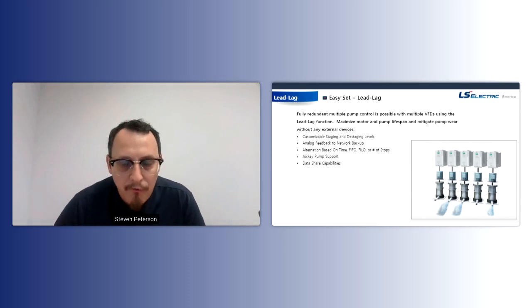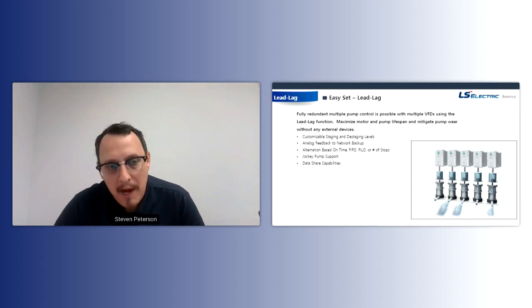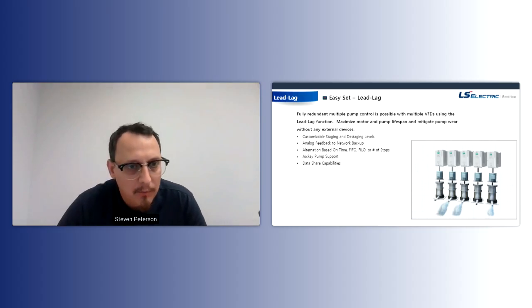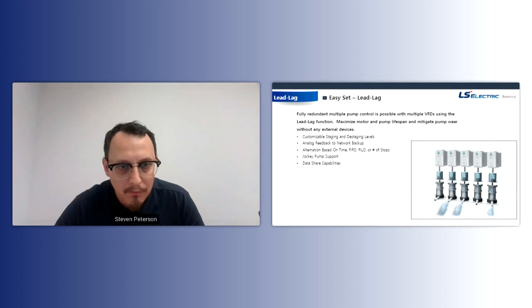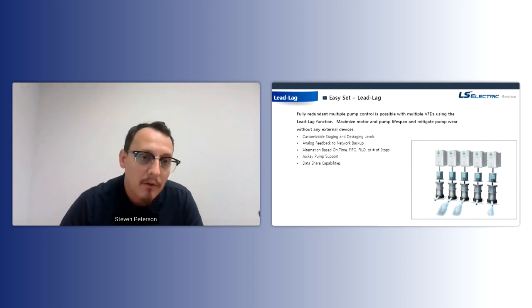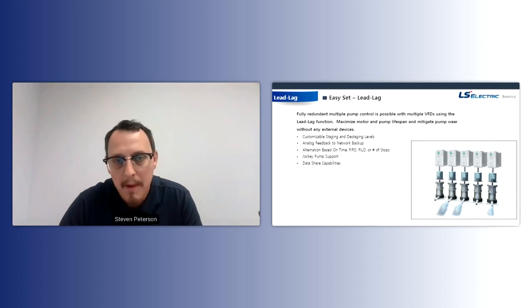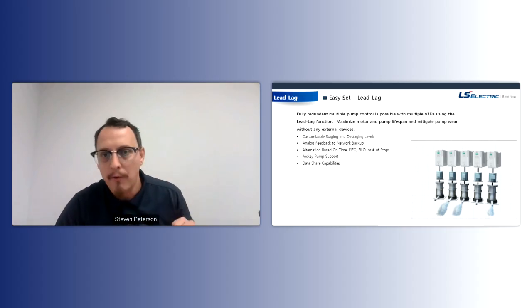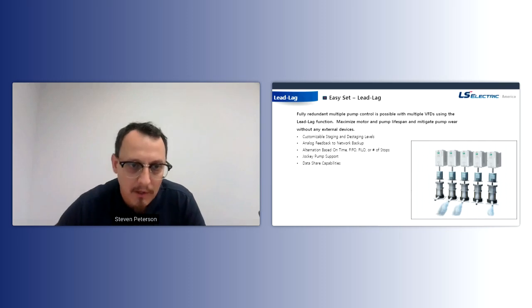Okay. So first, you should note that after you set up the macro, everything is fully customizable. So your staging and destaging levels, your on levels, your off levels, when you need more pumps, when you want to drop out pumps, is all fully customizable. Additionally, you could run analog feedback, or you could have network feedback, and we are adding functionality where you could automatically switch from analog feedback to a backup network feedback. So if feedback is lost, you could look at the backup feedback. So it's fully redundant in that regard.